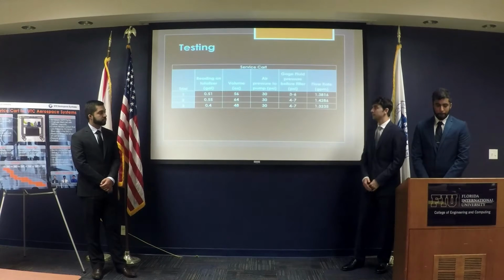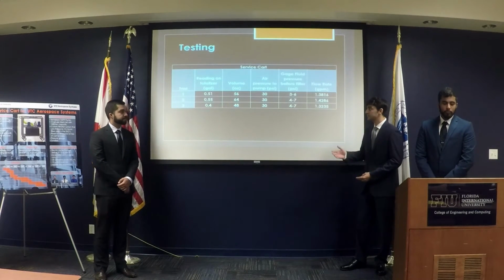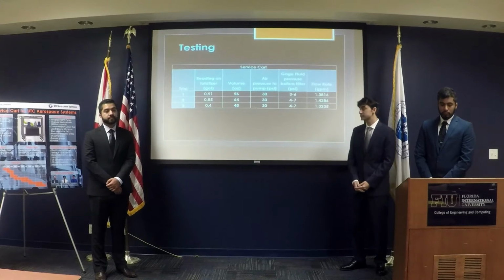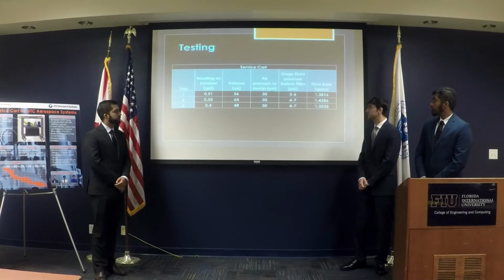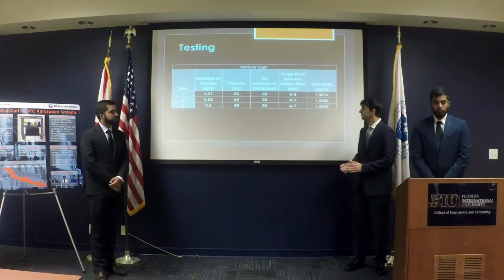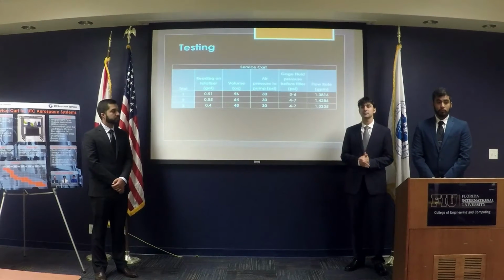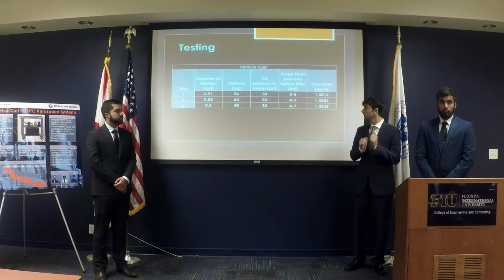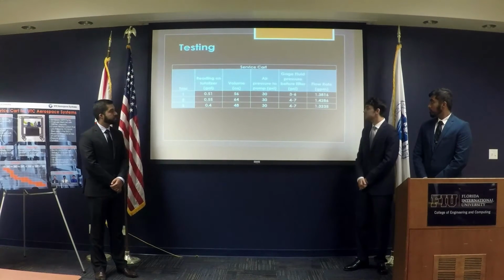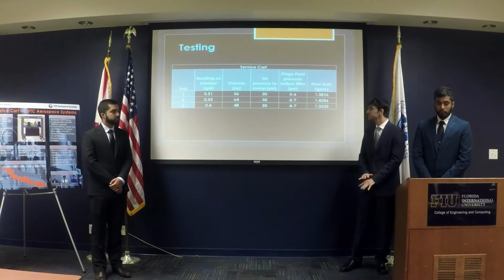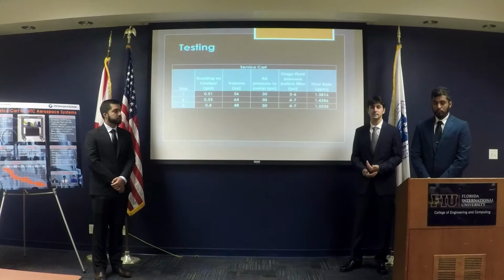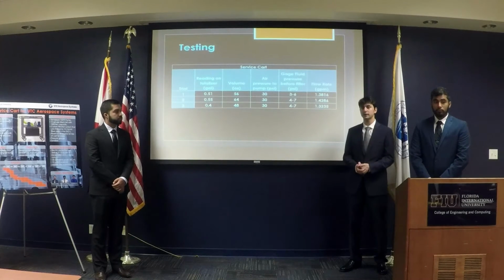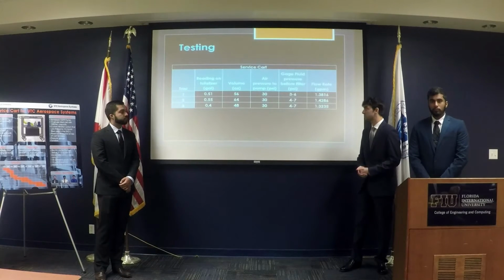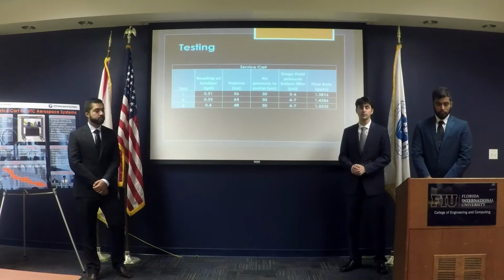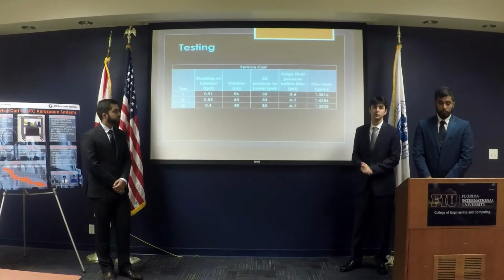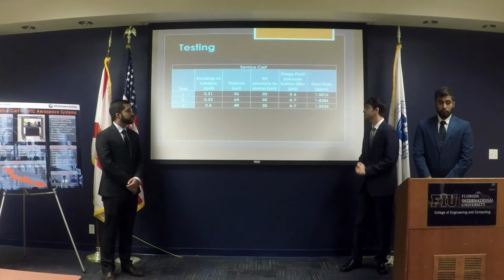Here's some performance data of the cart. We have a totalizer and a pressure gauge, so here's some data just as reference to see how accurate our totalizer is, as well as the pressure gauge readings, which varied from 3 to 7 psi. The reason for that fluctuation is because the pressure gauge will read and fluctuate as the pump operates between strokes. And we're getting a maximum pressure of consistently around high 6, low 7, while our theoretical was a little over 6, but that was calculated after the filter. And since our gauge is before the filter, we would disregard that 1.0 psi pressure loss, which gives us a theoretical pressure of around 7 psi.